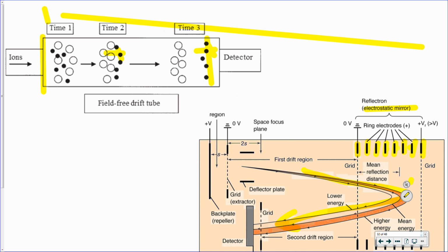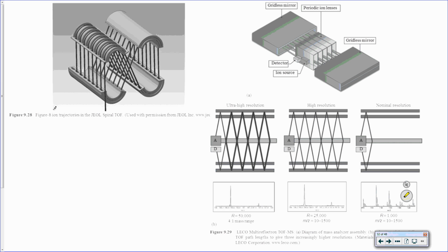So now instead of having to have a 30-meter tube, I can get a 5-meter tube, or a 10-meter tube, and do one lap. Or more effectively, you can have something that's 1 meter long on an instrument. With a reflectron, it's effectively 2 meters long. And that gets you to a resolution of 100,000. But the engineers have gone crazy with this.